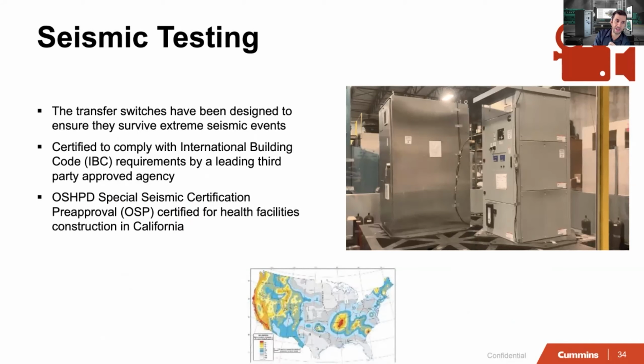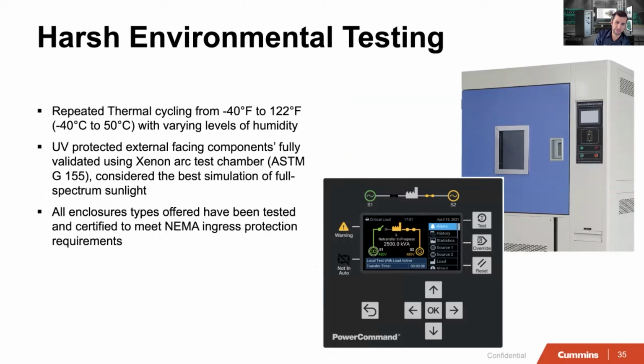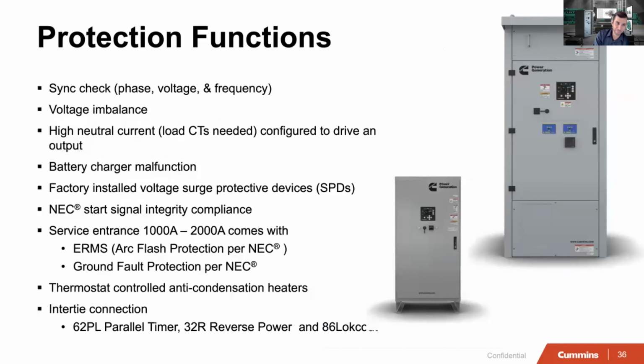It's been tested to meet IBC and OSHPD. OSHPD is the California certification for healthcare facilities that also has a seismic element in it as well, right? So it's been on a shake table to meet these highly seismically active regions. The control itself and other components that go into the transfer switch have also been subjected to harsh environmental testing in very sophisticated chambers to simulate harsh environments. And this control has been through repeated thermal and humidity testing and other testing to make sure that it has the highest reliability for you and for your facility.